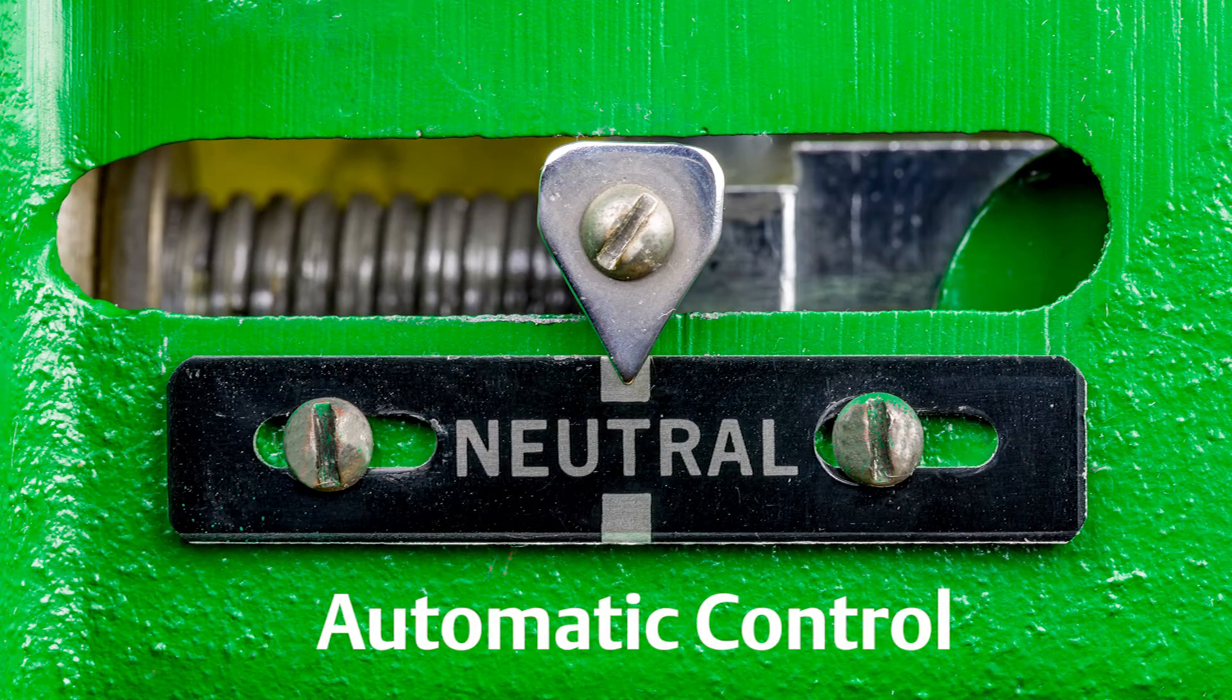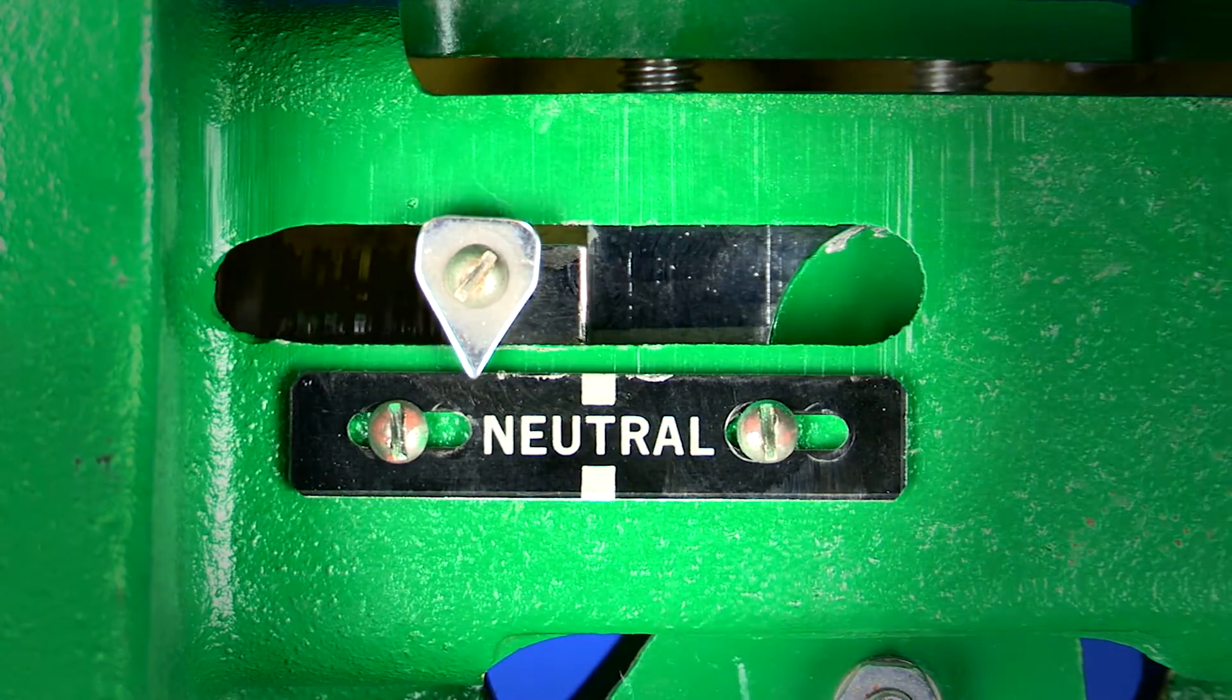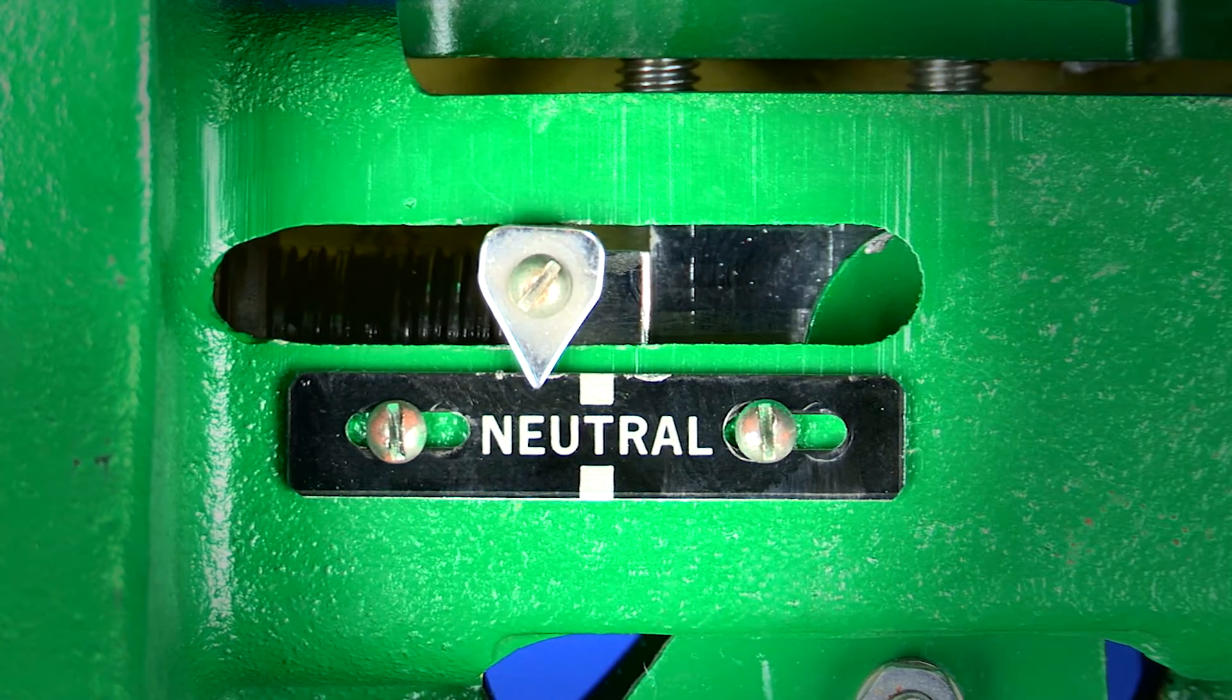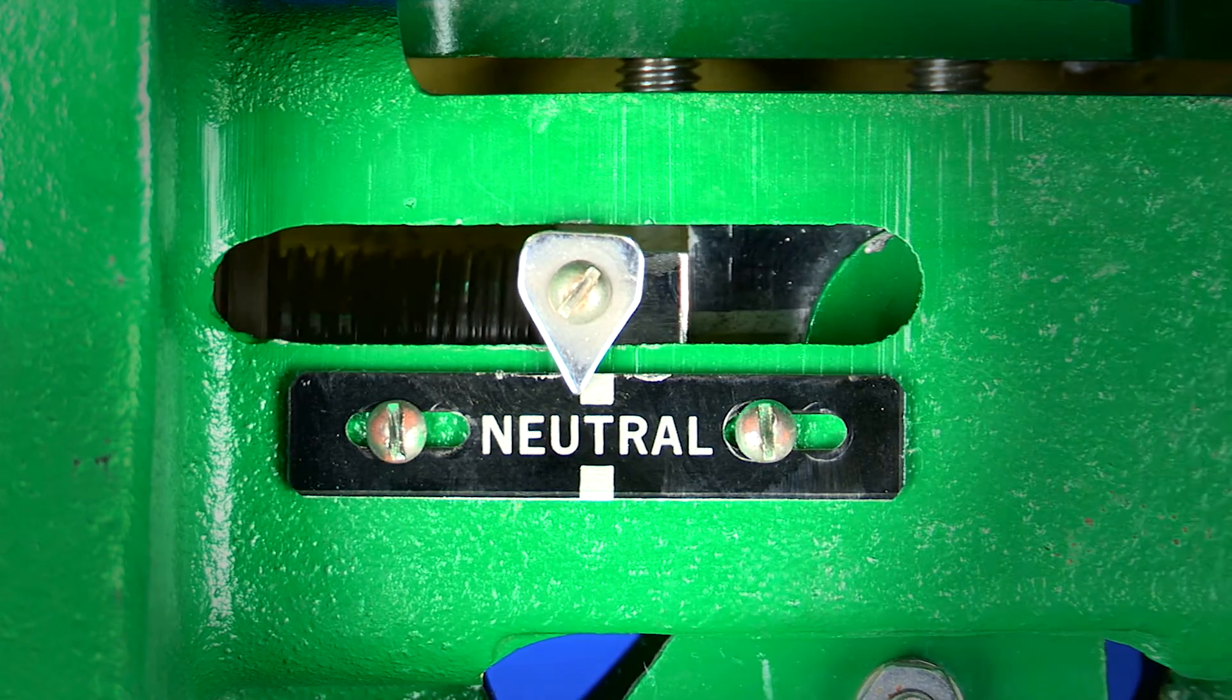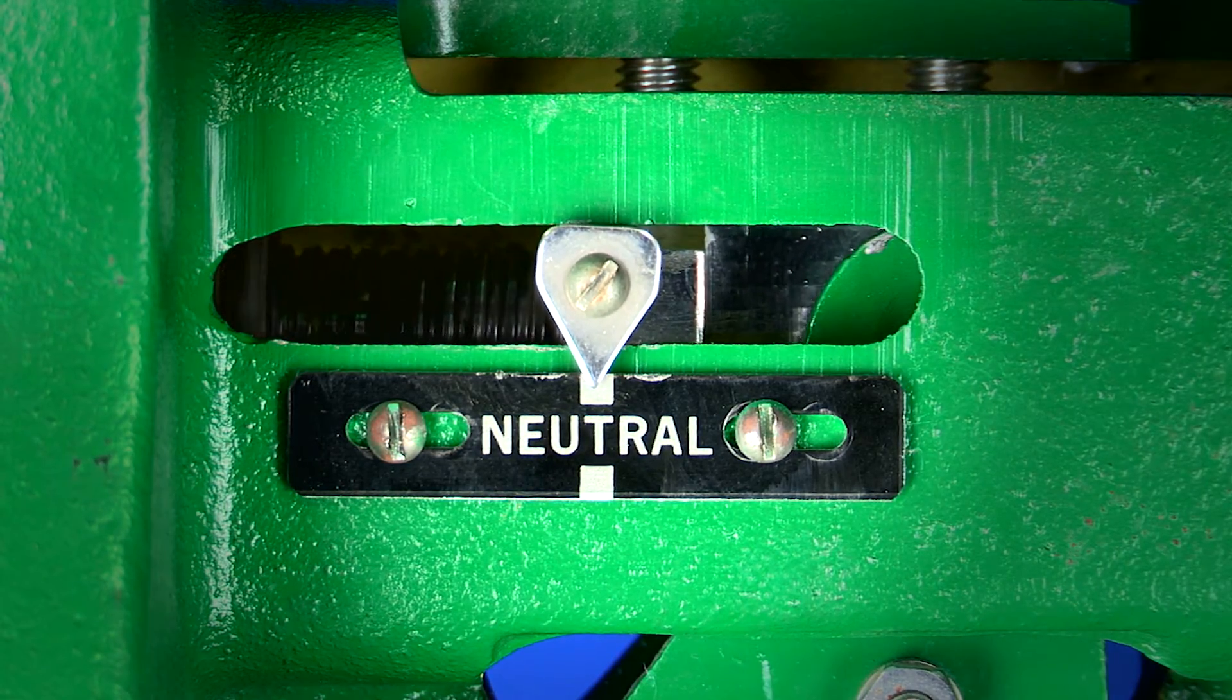However, with the handwheel in the neutral position, automatic control of the valve's full range of travel is possible. Make sure to return the handwheel position to neutral if you want to return to fully automatic valve operation across the entire travel range.